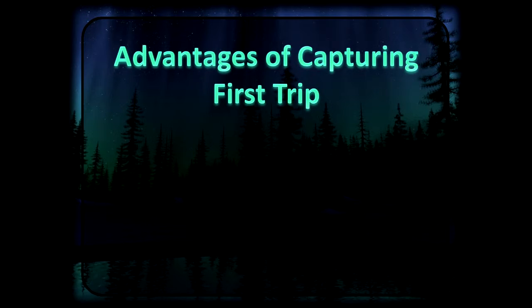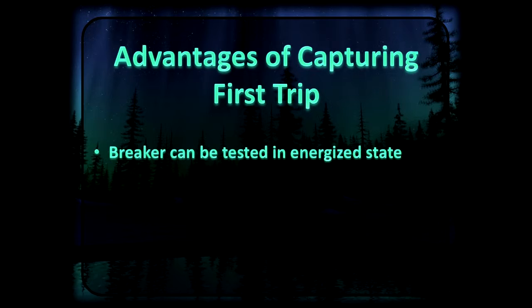So looking at the advantages of capturing your first trip and using this device, which is a newer technology, first off, like I stated, the breakers can be tested in an energized state. You're able to test the lubrication of this breaker when you test its first trip, or its first operation. A lot of times these breakers will sit 2 or 3 years without an operation, and you want to test the bearings and the lubrication, and this allows you to do it.